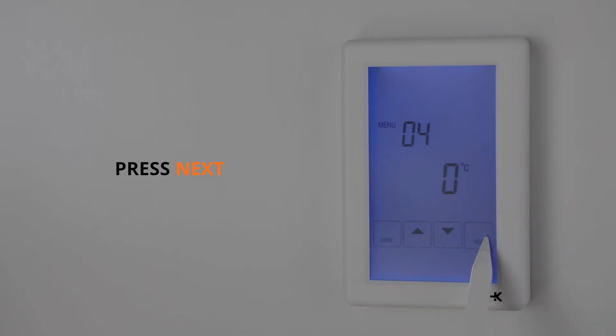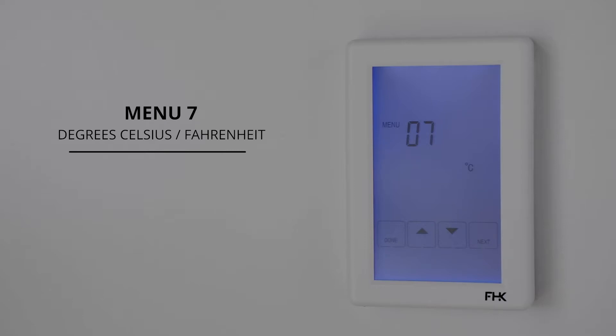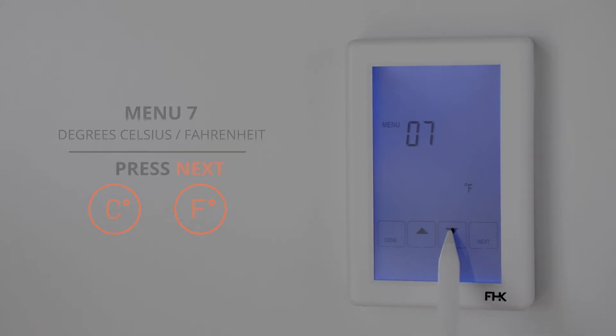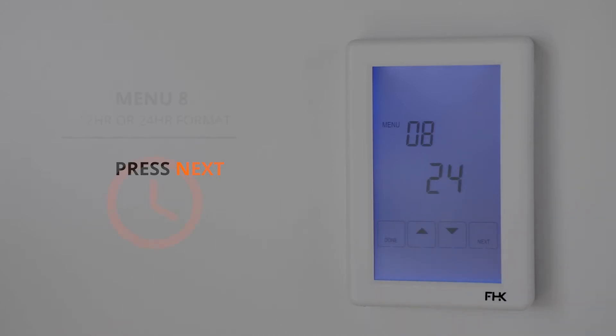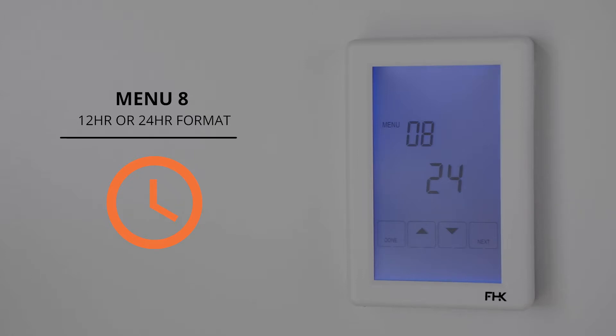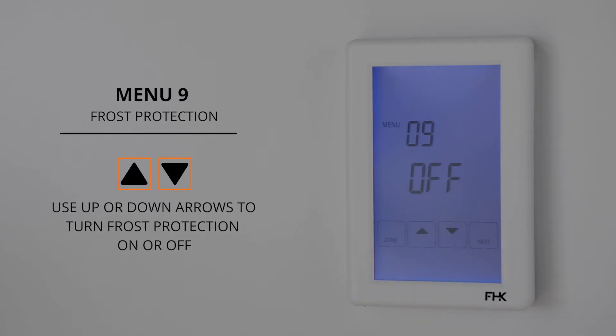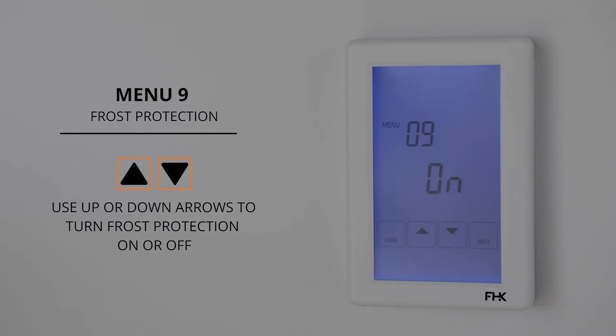Press next to move on to menu 7. Menu 7 changes the temperature type to either degrees Celsius or Fahrenheit. In this video we have set it to Celsius. Press next to move on to menu 8. Menu 8 is used to adjust the clock to either 12 or 24 hour format. Simply click the down arrow to change to your preference. Press next to move on to menu 9. Menu 9 is used to turn on frost protection. When this option is turned on, your unit will not allow your floors to fall below 5 degrees Celsius. You will only need this if you are in a colder area; if you are in a warmer climate where the floors won't likely get below 5 degrees, you can keep this option off.